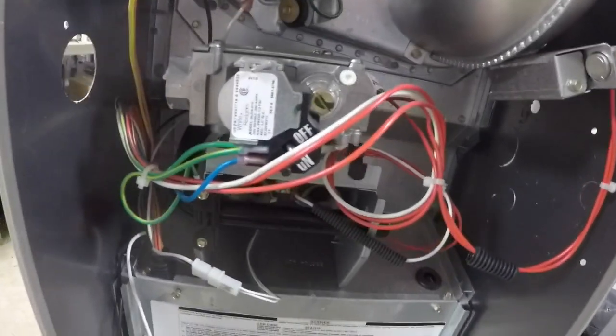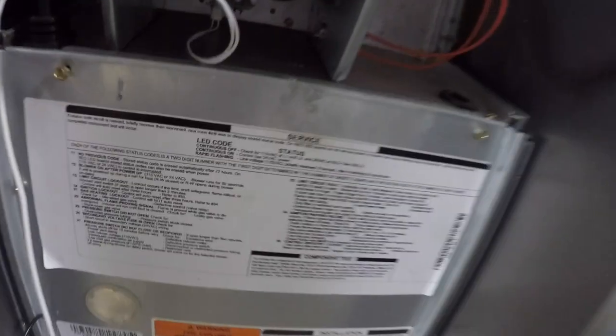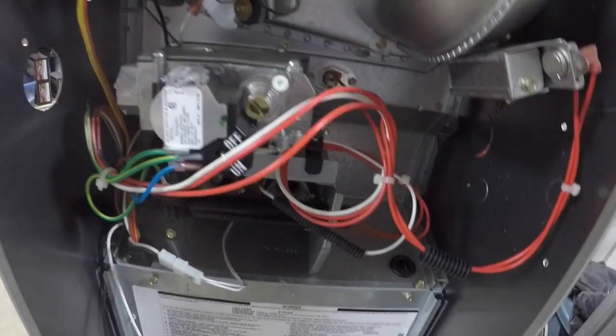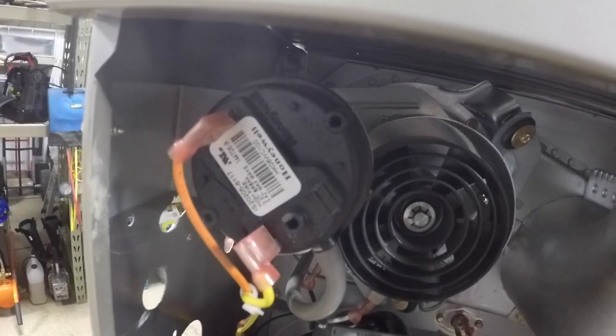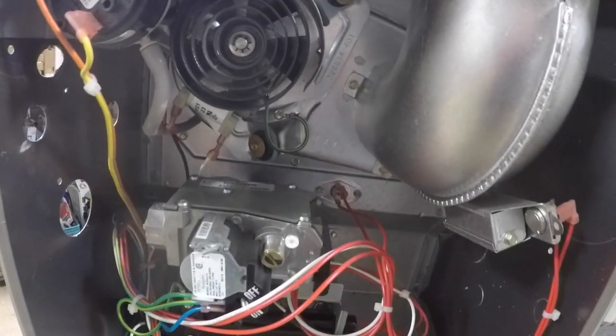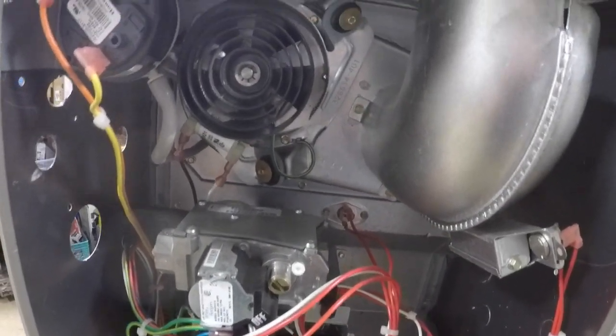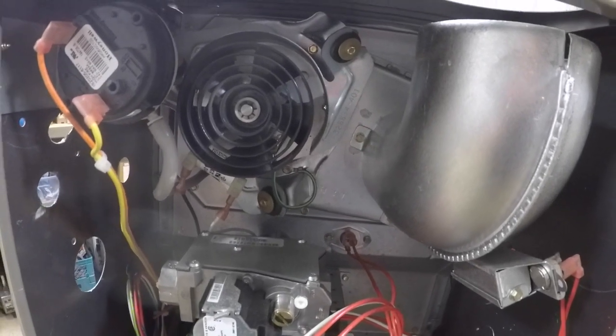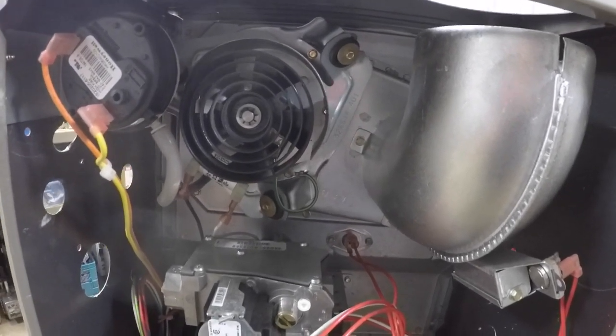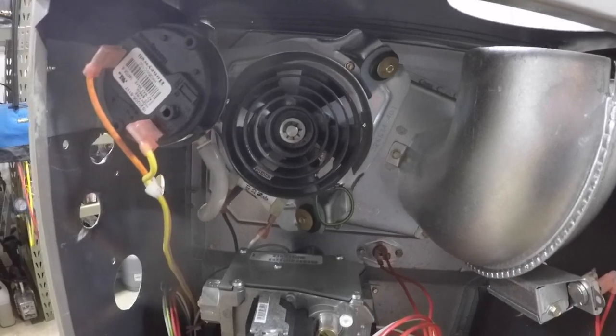And sometimes there's codes that would blink down here. There's a little series of codes that are listed up right there that might say pressure switch not closing. So people are tempted to just change out that pressure switch. Without the correct instruments to test what's going on, you might incorrectly fix your furnace in a way that makes it unsafe to operate. That's what I'm talking about today.